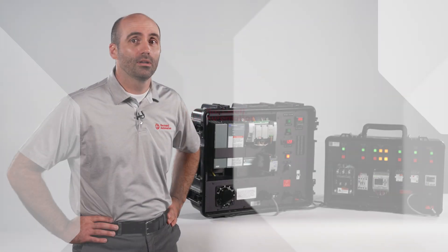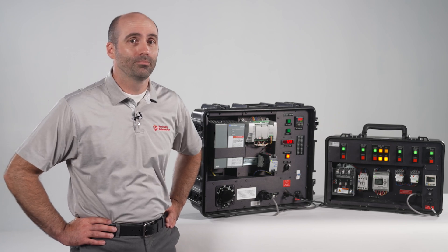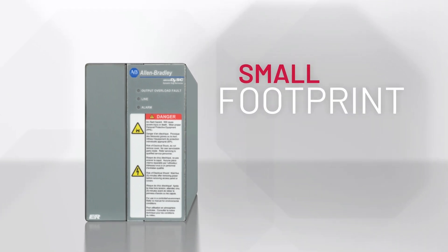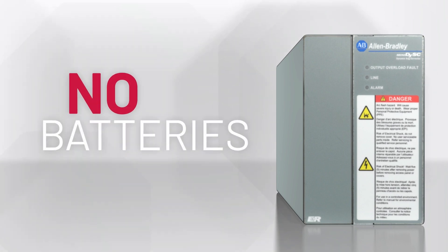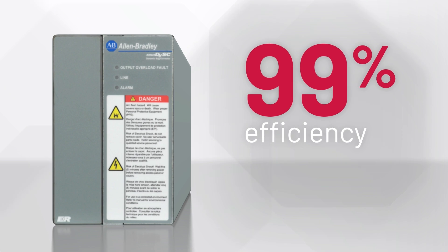We've just demonstrated how the DySC can protect your site against voltage sags. But there are more advantages to consider. The DySC is available from 250 watts for component level protection up to 2 megawatts for entire process line protection. It has a small footprint, which minimizes the space needed for installation, perfect for both greenfield or retrofit applications. It uses capacitors for energy storage, so there's no need for additional battery space and no expensive battery replacements throughout the life of the product. Finally, it operates at over 99% efficiency, so your process can be protected and your company can meet its sustainability goals.